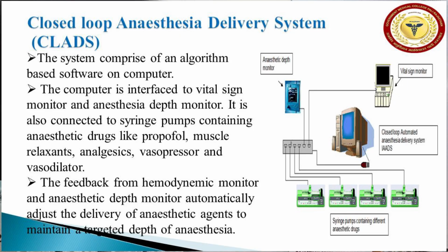Closed loop anesthesia delivery system, CLADS. The system comprises algorithm-based software on a computer, and the computer is interfaced to the vital sign monitor and the anesthesia depth monitor. It is also connected to the syringe pumps containing drugs like propofol, muscle relaxant, analgesic, vasopressor, and vasodilator. These are the pumps, and this is the vital monitor and anesthesia monitor. These all are connected to the computer.